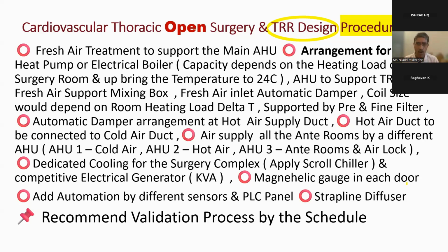So the entire load, as I was telling at the beginning, the load calculation will be separate for these types of CVT surgery rooms. Apply an air-cooled scroll chiller, which is better than a DX system and more controllable, and can operate during a power failure. Magnehelic gauge in each door, and automation of the different sensors and others. So you understand that even reading out all these will take a lot of time.